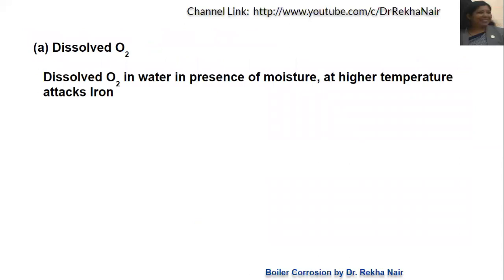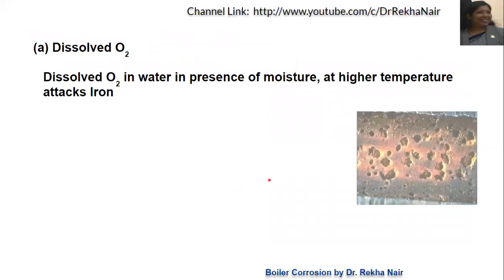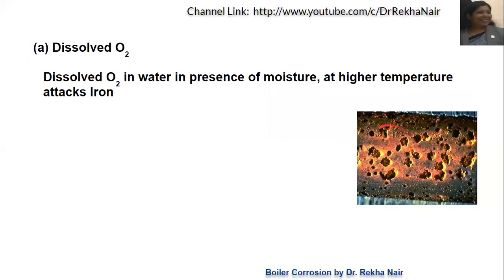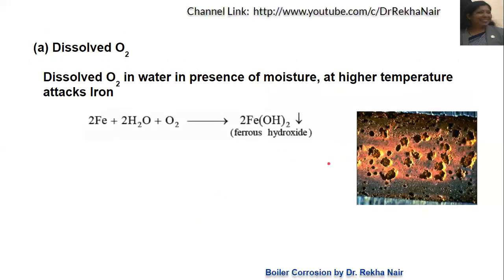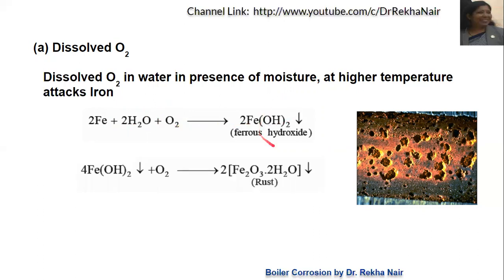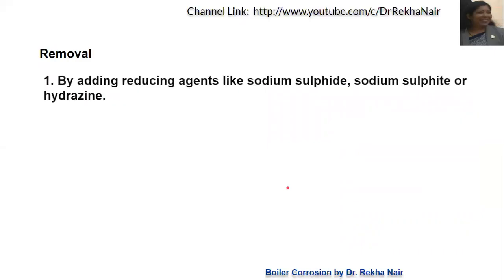First, dissolved oxygen in water in the presence of the boiler at high temperature attacks iron. You can see the reaction here. Iron will react with water in the presence of oxygen to form Fe(OH)₂, that is ferrous hydroxide, which will further react with oxygen to form rust. So, if there is oxygen present in water, there will be corrosion.